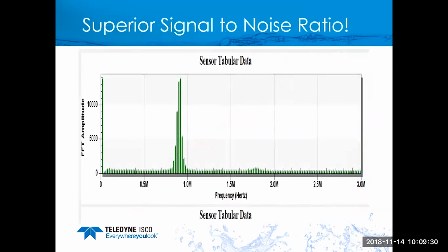Okay, so why does the laser work so well? Well, the signal to noise ratio is incredible on the laser. The peak that you see here is the return signal from the 5,000 velocity scans. On the bottom scale is your velocity, but it's in frequency. So to the right is faster velocity, to the left is slower velocity. As the speed of the water changes, that signal will move back and forth along that scale. The key thing about this is that our noise level is really, really low.